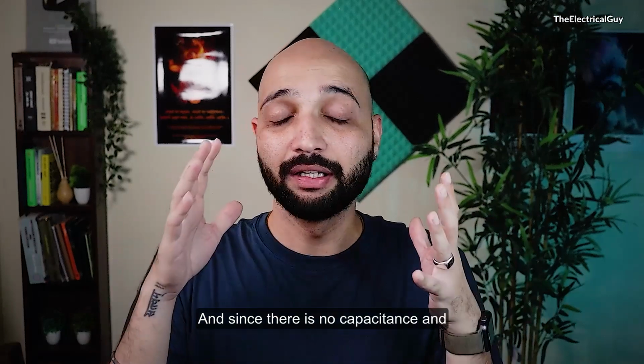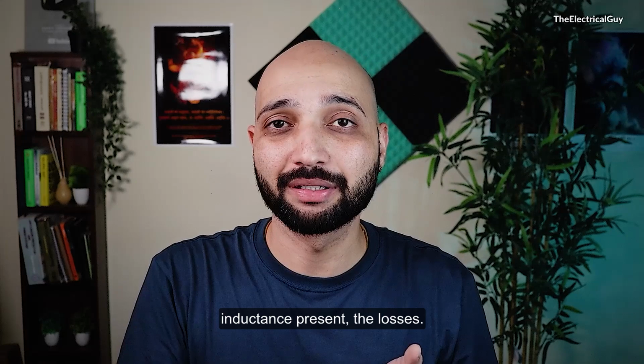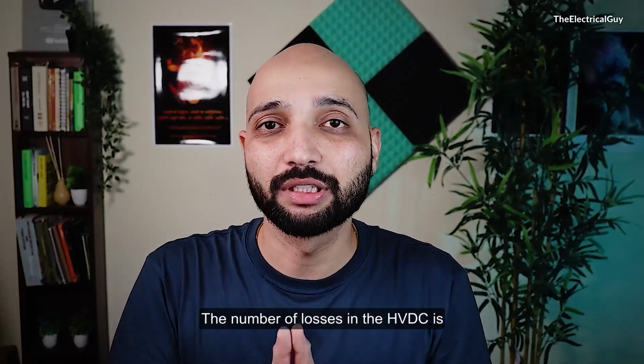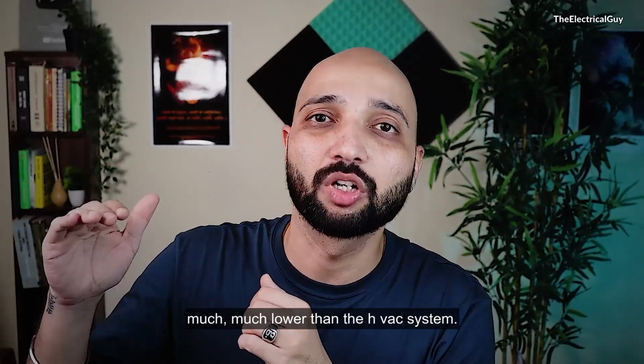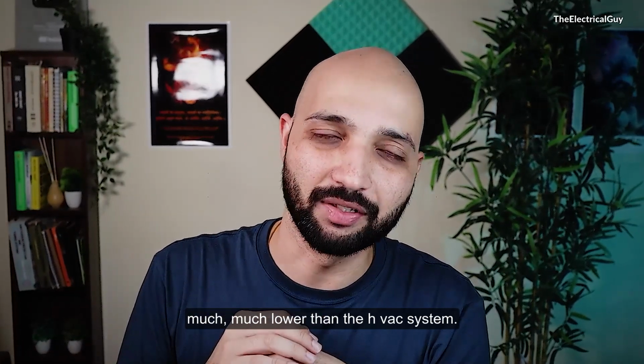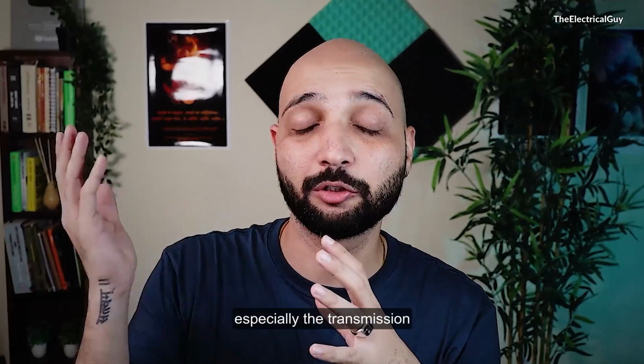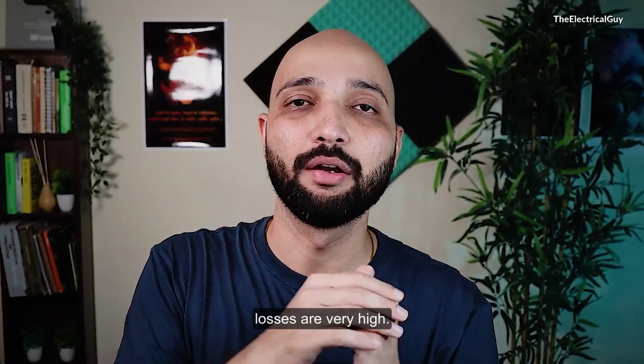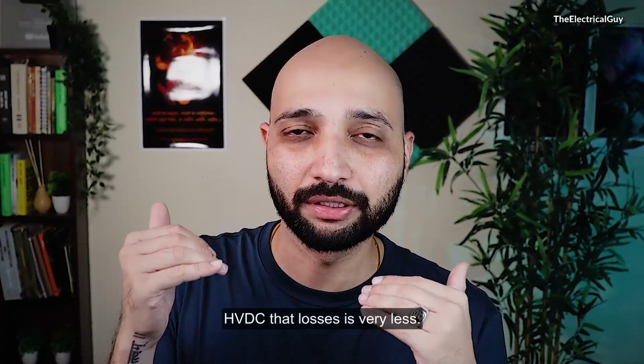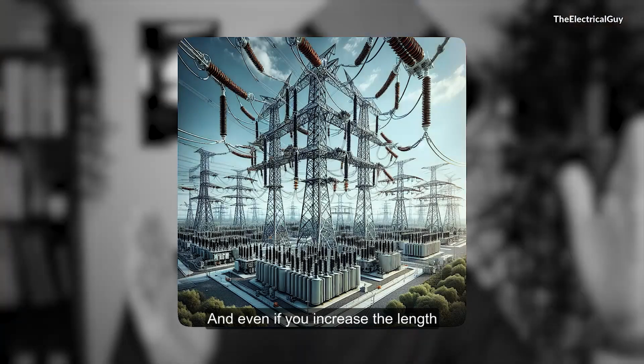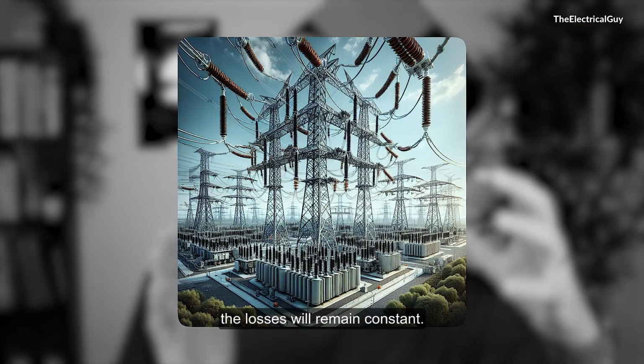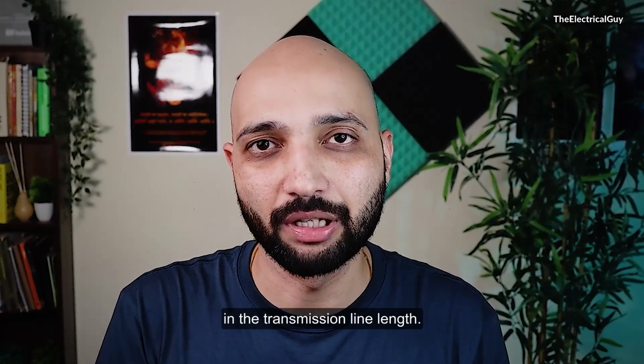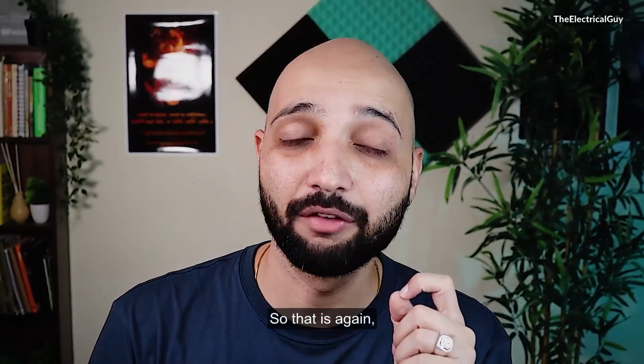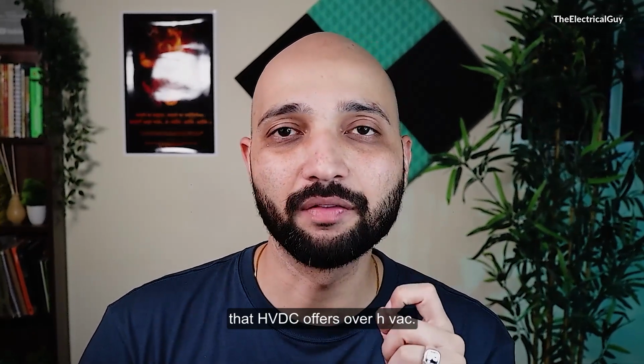Since there is no capacitance and inductance present, the number of losses in HVDC is much lower than the HVAC system. In HVAC, especially the transmission losses, are very high. In HVDC, those losses are very less. And even if you increase the length of the transmission line, the losses will remain constant, it will not increase with increase in transmission line length. So that is one of the important advantages that HVDC offers over HVAC.